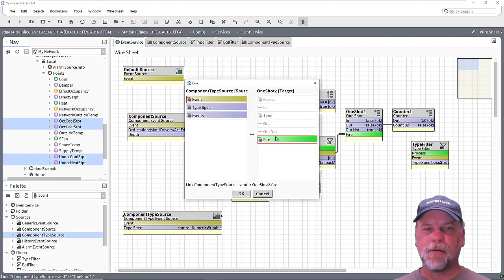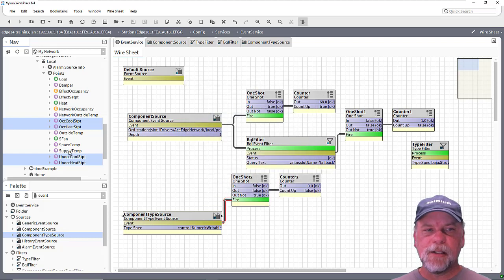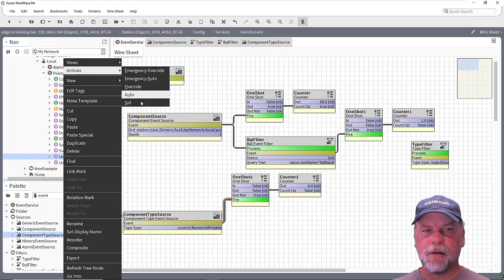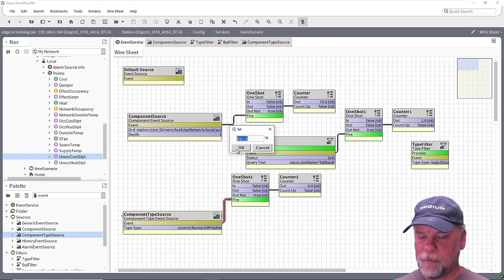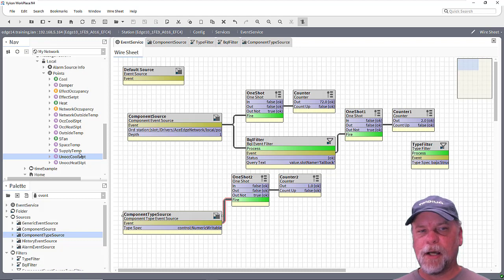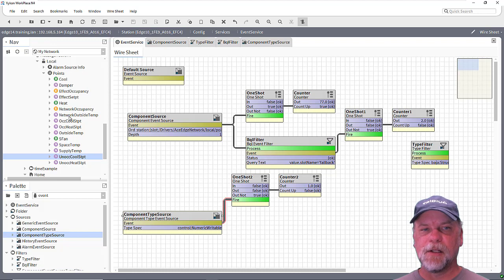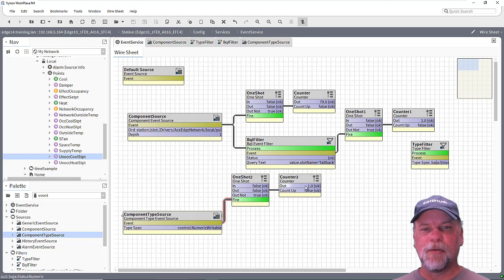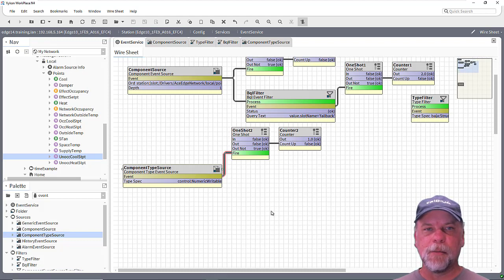So we'll link from the topic to the fire action again here. And in this case, if I invoke any sort of action — set the fallback or override any of the numeric writables — underneath in the station, actually anywhere in the station, not just under a certain component, since this is subscribing to all numeric writables in the station, then it'll fire the action here on the one shot and we'll see that the counter will increment.